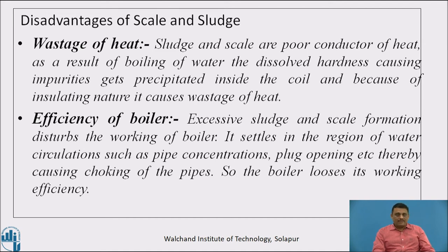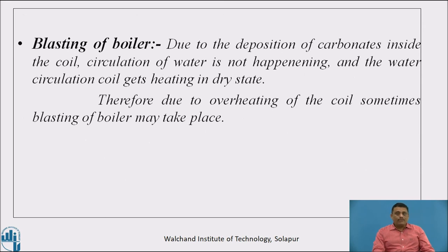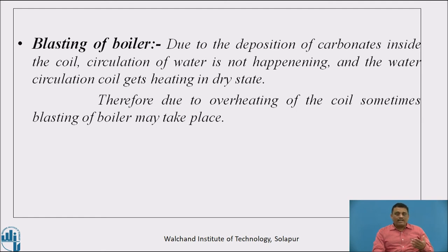The third effect is blasting of the boiler. Due to deposition of carbonates, circulation of water inside the coil does not happen, and the water circulation coil gets heated in a dry state. Therefore, due to overheating of the coil, blasting of the boiler may take place. This is particularly related to safety — if scale and sludge formation is ignored, the coil gets overheated and may cause the boiler to blast.